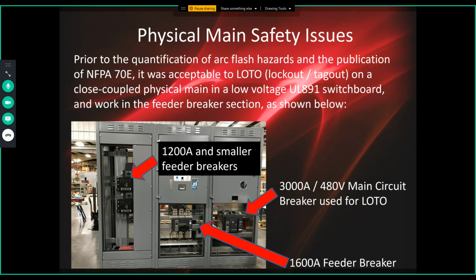Prior to quantification of arc flash hazards and the publication of IEEE 1584, the original one, and of course we had a new version of 1584 recently published, and of course NFPA 70E, it was acceptable to lock out the main on a low voltage UL 891 switchboard and work on the feeder section. So you can see the picture there. On the lower right of the picture, you can see the main breaker sitting there, and we could see a 1600 amp feeder to the section to the left of it, and then all the way on the very left, this is, by the way, a Square D QED2 I-Line, a pretty classical switchboard.